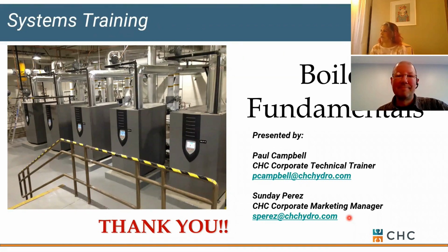Awesome. Okay, for domestic water heater with higher return temps, is a condensing boiler less desirable? If I said that right. Yeah, it's a good question. To me, you have to look at your efficiencies, and so if you're keeping a storage tank at 140 degrees, in reality you might get 90 to 100 coming out of it every time it goes to a water heater. But if you're keeping that storage tank at 160 to 180, then you might have temperatures that are warm enough where a condensing water heater does not make sense.